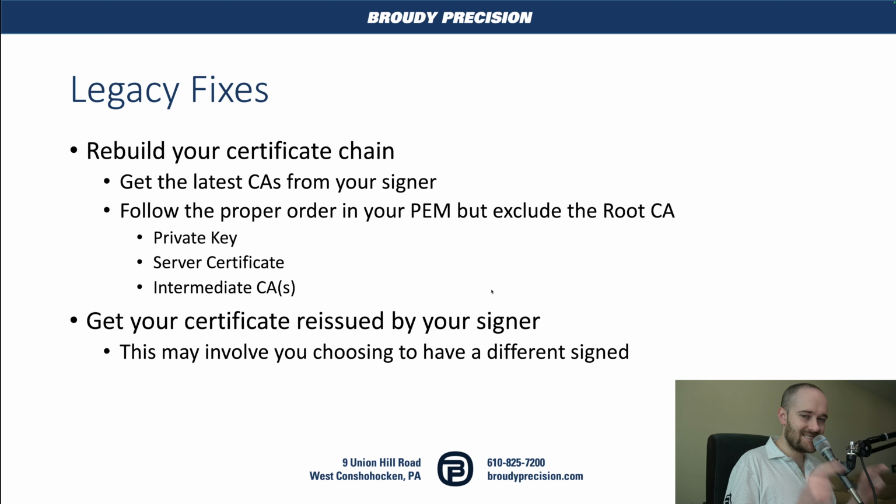You just can't send the SHA-1 certificate over the wire in your connection when you pull up your station in Niagara. So if you build up your PEM file without that root CA in it, I've seen success in those legacy instances. Your other option is to get the certificate re-signed completely and not have it use a SHA-1 certificate at all.